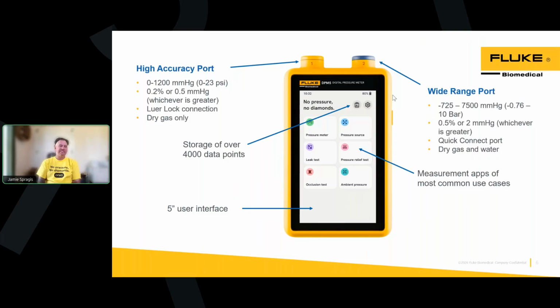Well, there were a couple of different reasons. One was probably price, putting that much technology. And secondly, we've noticed, through the voice of the customer, our customers are saying that a digital pressure meter is a great tool to have, but normally doesn't fit in that primary tool category, like an Impulse or like your ESA 700 series for electrical safety testing. So we just found the need of having One QA on the instrument was not really needed for the industry. But with One QA, you can bring that measurement right into it. You can basically take a numeric value, plug it into your One QA procedure, and you're ready to go. So again, there's ways to work in your DPM5 or other instruments with our automation software.